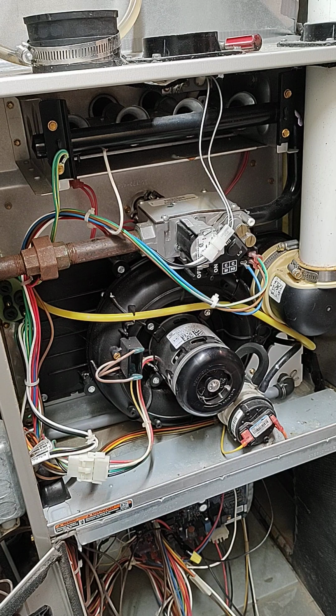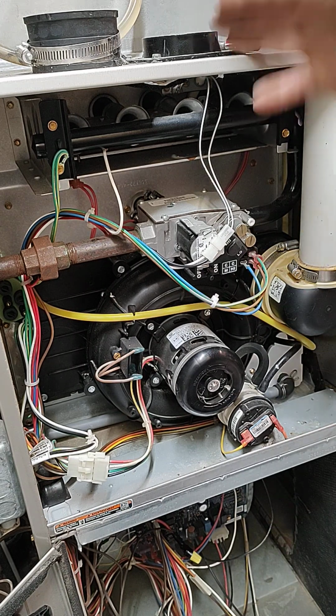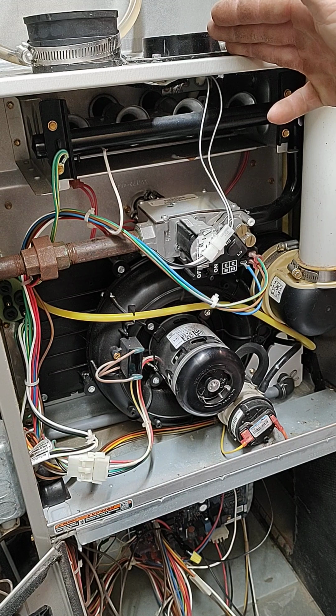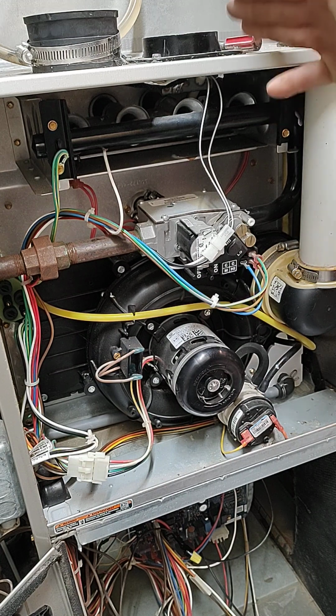But here, when we have 30, 40 below zero, and you have a 100, 200, 300 degree heat exchanger, sucking that cold air in there isn't too good on the equipment. So usually when the inspector leaves, we just fill the pipe with insulation. But it's still good practice—generally I'd suggest just piping the intake from the furnace outside. That's a big thing right there.